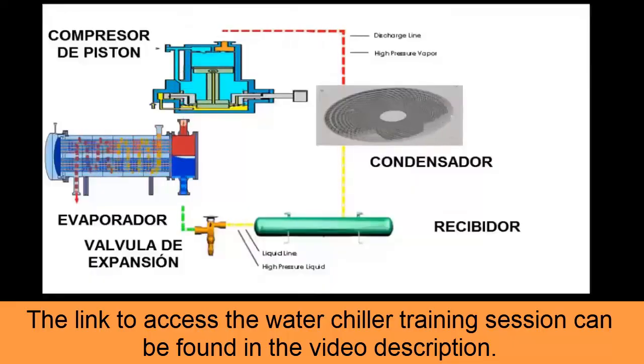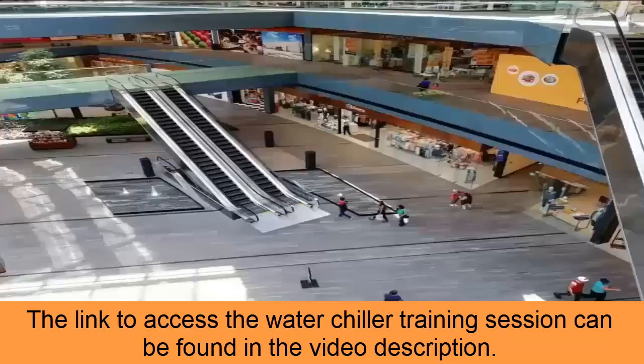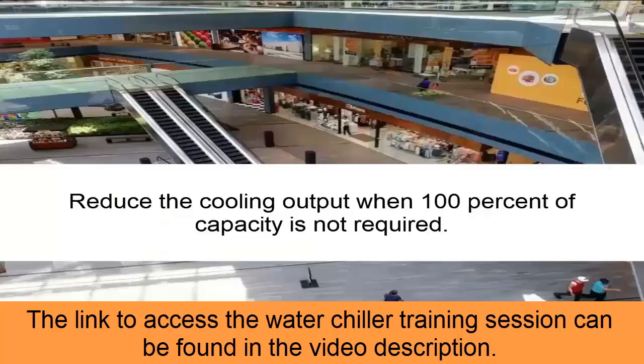Capacity regulation of the piston compressor by simulating heat at the evaporator inlet without energy savings. This model is based on simulating thermal loads when there is not enough real heat in the evaporator. Imagine again the shopping mall at 9 a.m. on a Monday with few people present. At that moment, we do not need the full cooling capacity of the chiller.